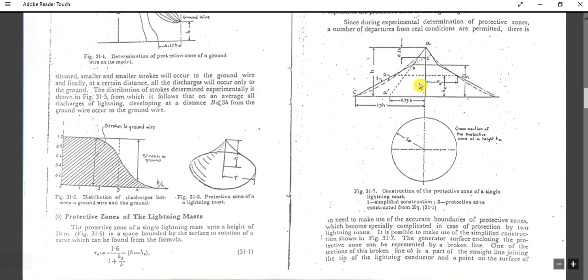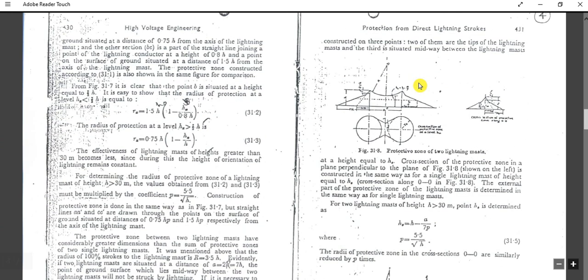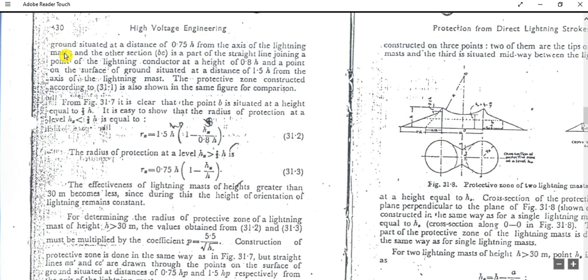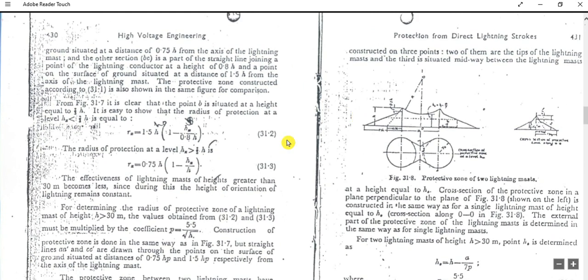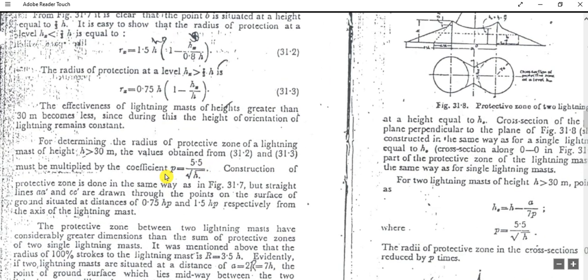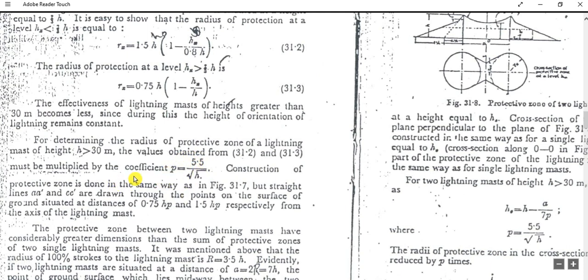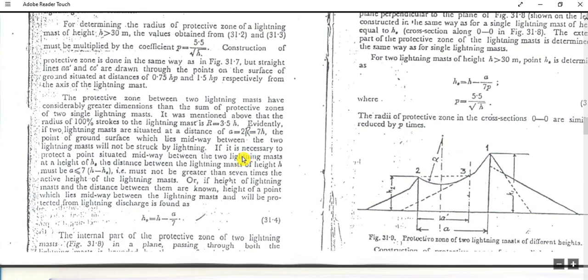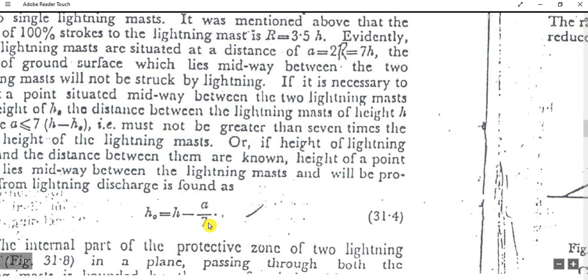This is a little bit complicated, but if you understand the basic theory it will be easier. For determining the radius of the protective zone of a lightning mast of height h greater than 30 meters, the values from these two equations must be multiplied by the coefficient p, which equals 5.5 divided by the square root of h. Also, h₀ equals h minus a divided by 7.